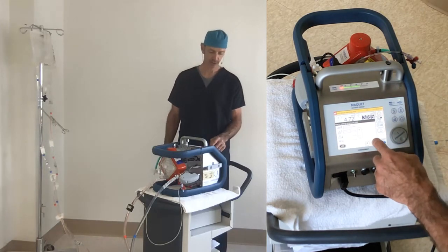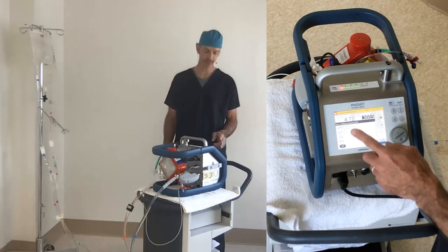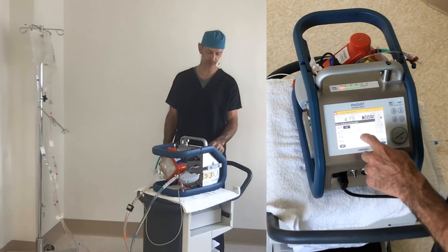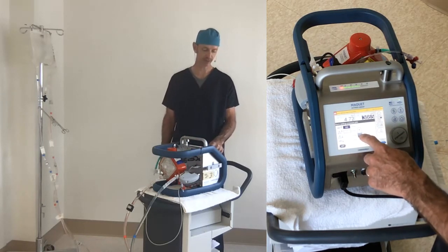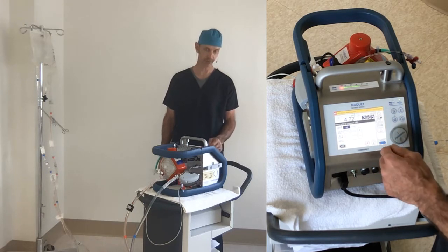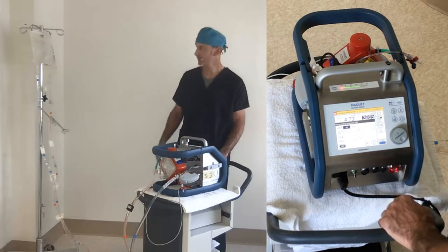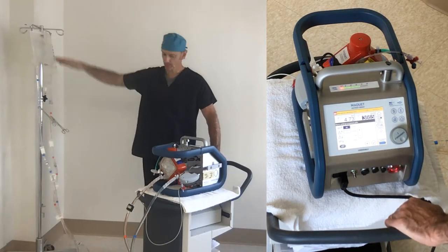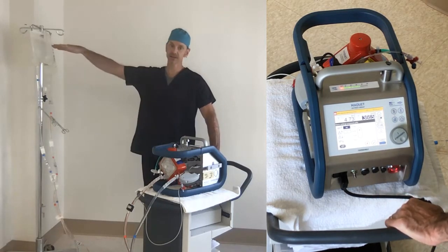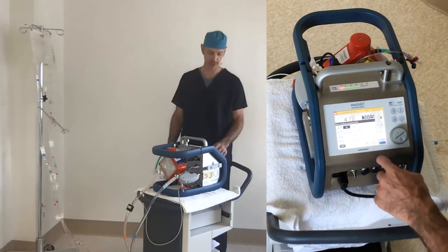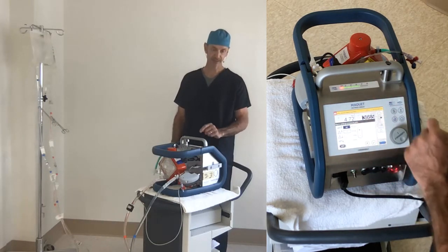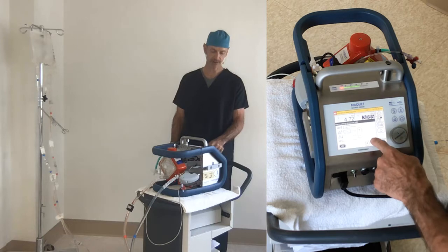So we always had flow there. I want to be convinced that the pressures can actually stop the pump. Let's turn this range down to 50, 44, that's good. I'm going to turn it down to 44 because this column of fluid pushing down on this gives us about 63, I think, is what I measured earlier.